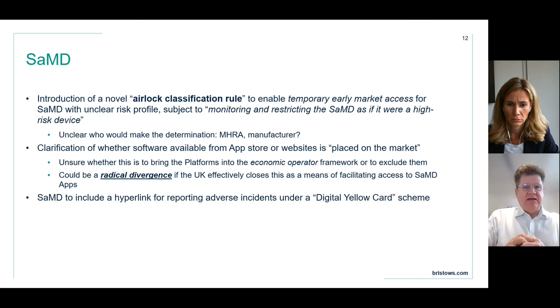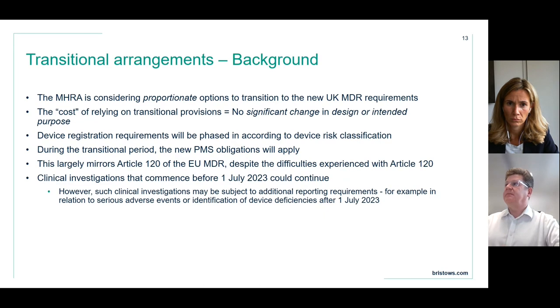My impression is that if the MHRA was to take the view that the platforms are economic operators rather than mere facilitators, this would radically reduce the number of software medical devices made available via these well-known platforms. The MHRA also proposes that the software must include a hyperlink to enable reporting of adverse events under an equivalent of the medicinal product yellow card scheme, albeit a digital version.